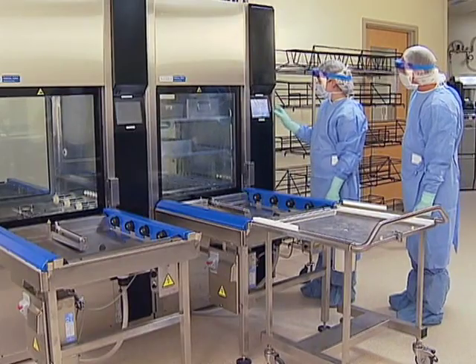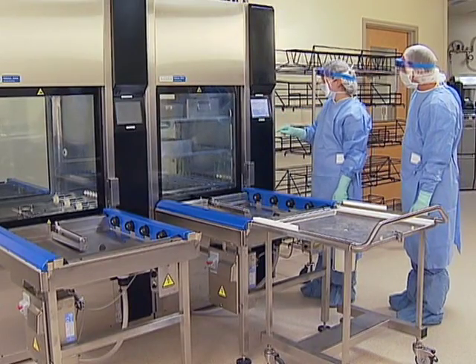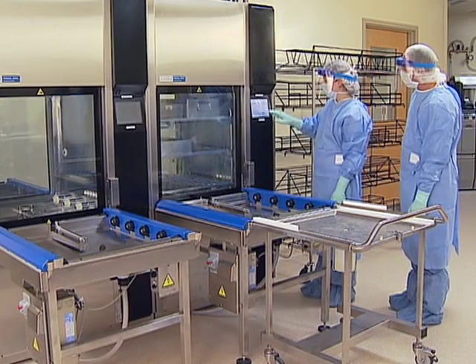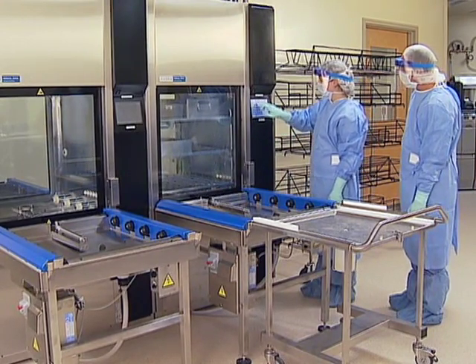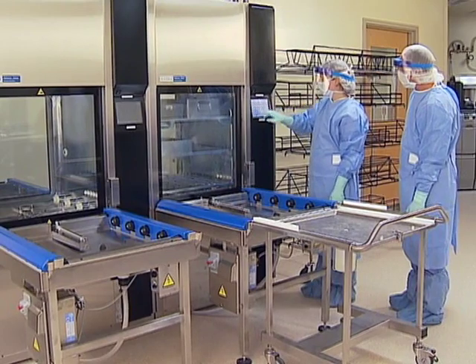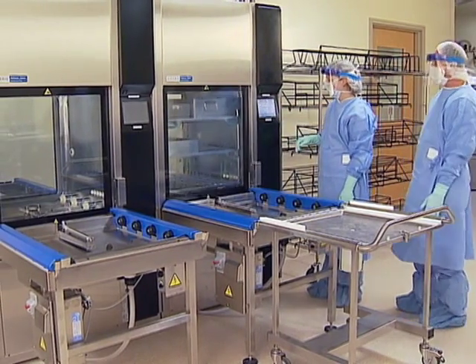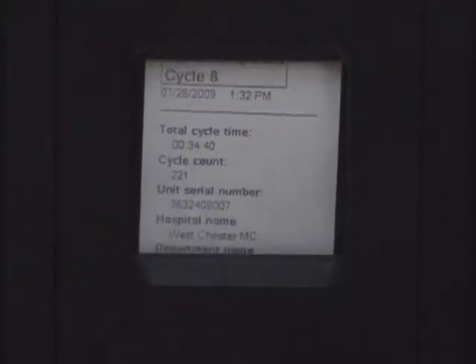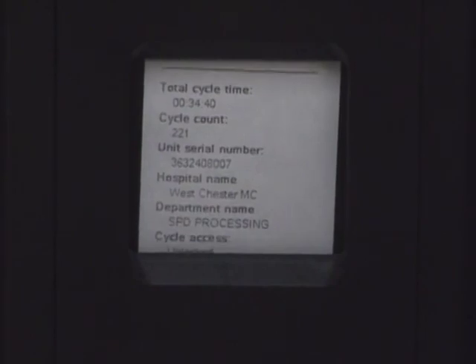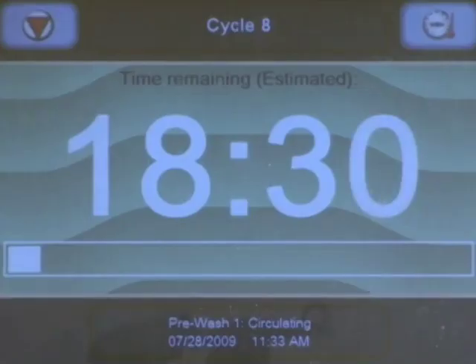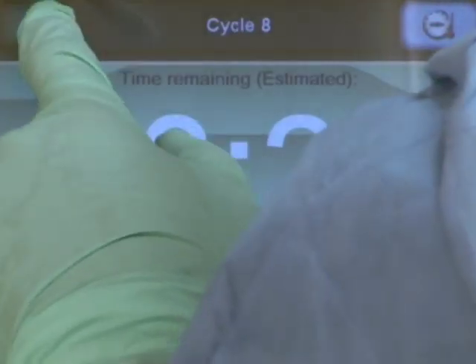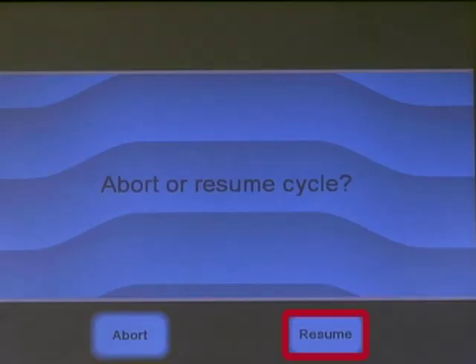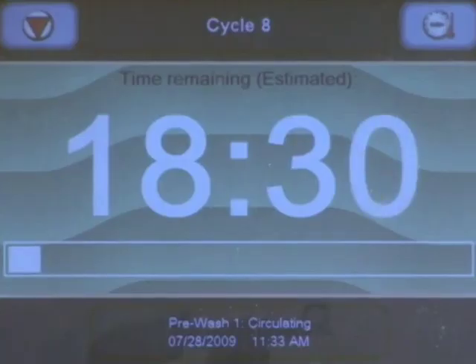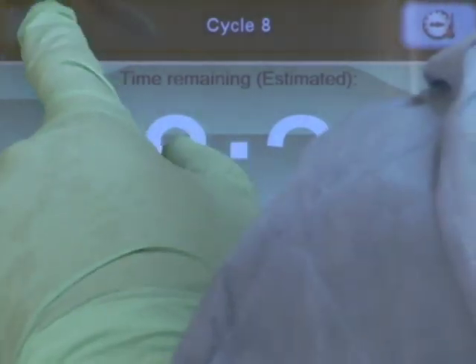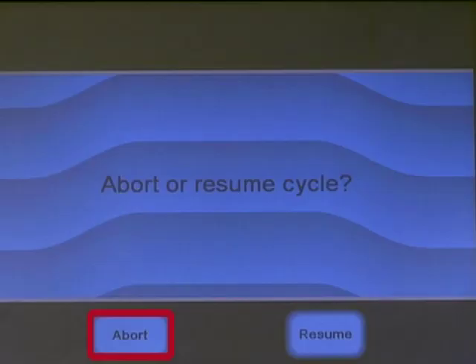If a cycle is aborted before the thermal rinse phase is completed, the load can only be removed or accessed from the load or dirty side to ensure that there is no cross-contamination. Your supervisor must log in to open the load side chamber door. The cycle printout records the warning and alarm information and whether or not the cycle was resumed or aborted. If you need to pause a cycle, press Stop on the control screen. Then press Resume to continue the cycle. If you need to abort a cycle without receiving an alarm, simply press Stop, then Abort.